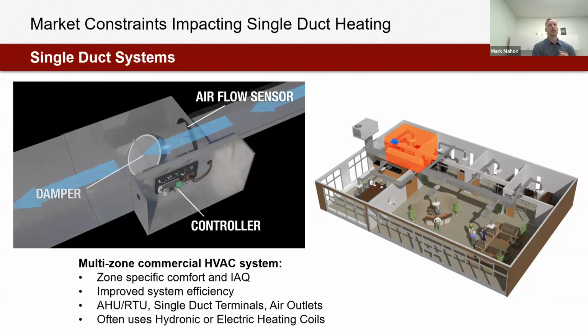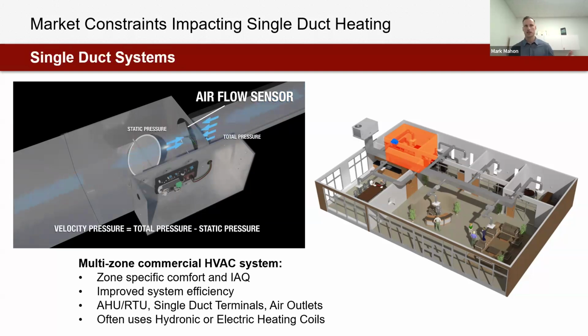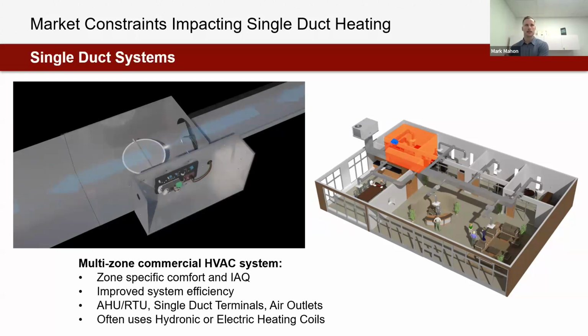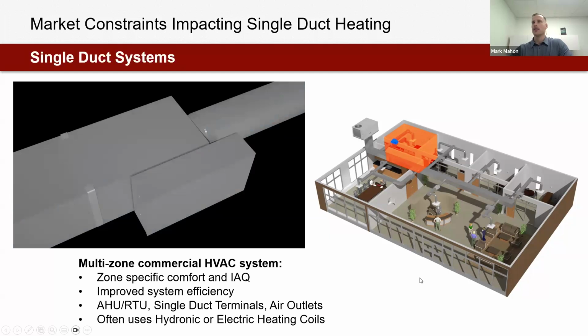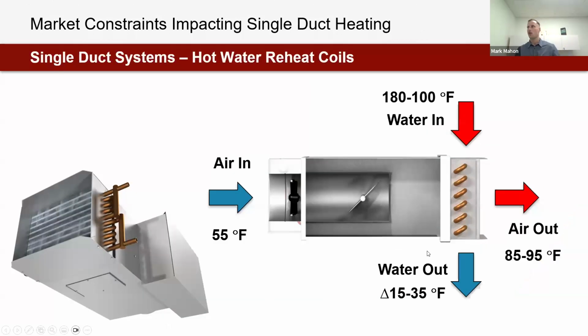the individual zone. The three major pieces from an air distribution perspective: we have a package rooftop or an air handler, we have single duct terminals, we have air outlets. And very frequently this is using hydronic or electric heating coils, especially when we look at the market that you guys do business in. So my one other high level piece, when I just want to give my pitch on a hot water reheat coil, of course, we have cold, saturated 55-degree air for design day coming into the single duct box. We're going to need to reheat that air to 85 to 95 degrees to be able to actually address the heating requirements of the zone.